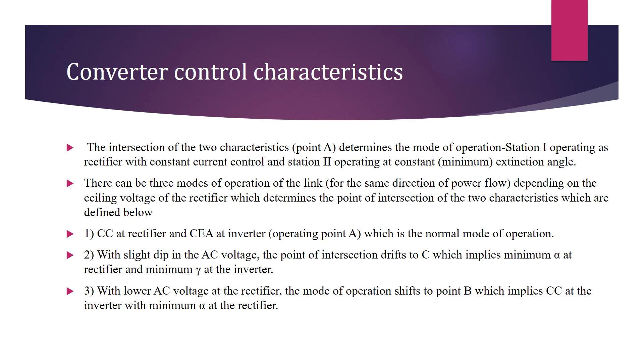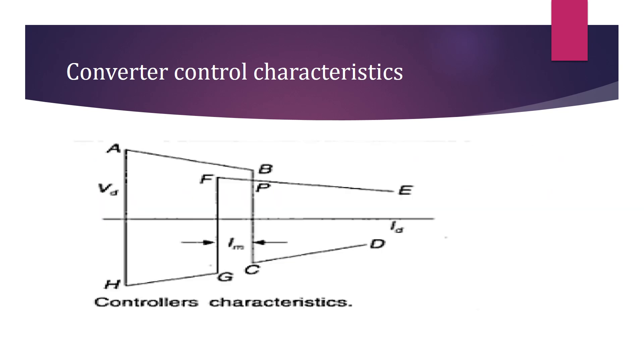From A to B, the first station acts as rectifier, whereas at the same time the second station will be acting as inverter. From C to D, the first station is acting as inverter and the second station will be acting as rectifier. Here from A to B, the converter is controlled by the constant current control technique.